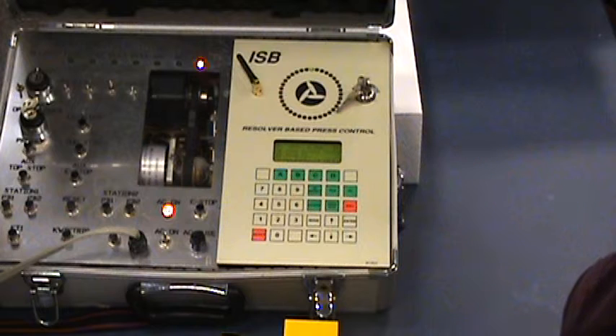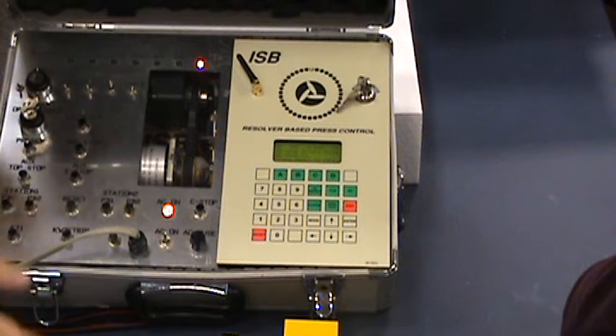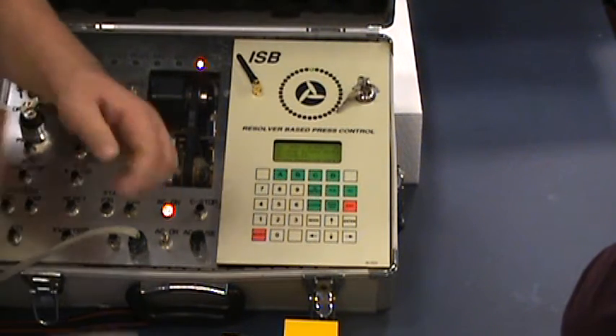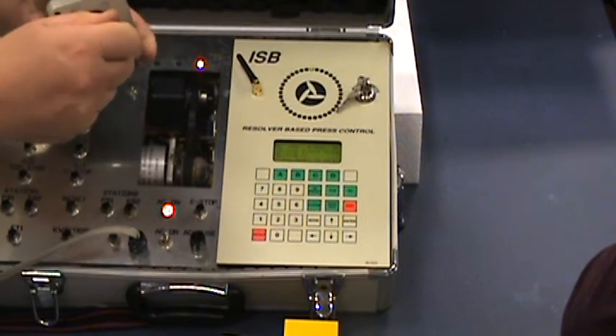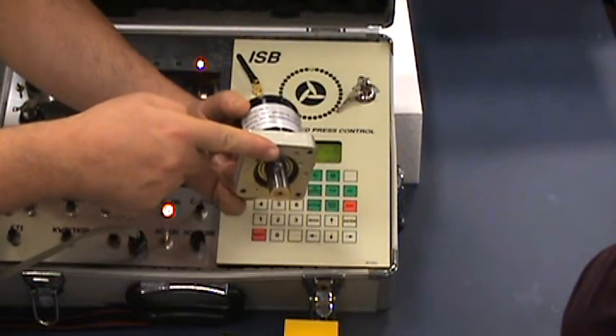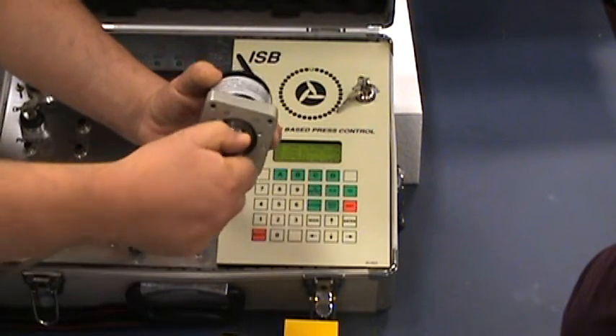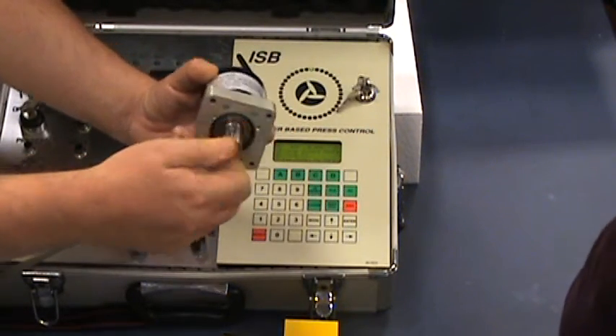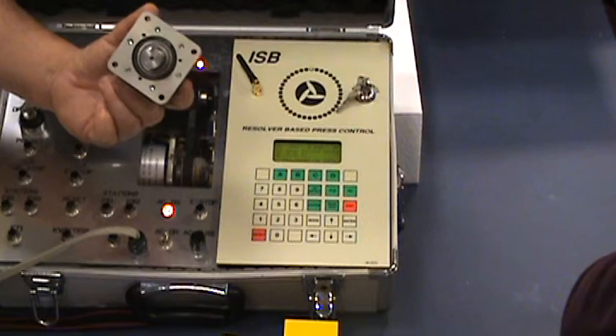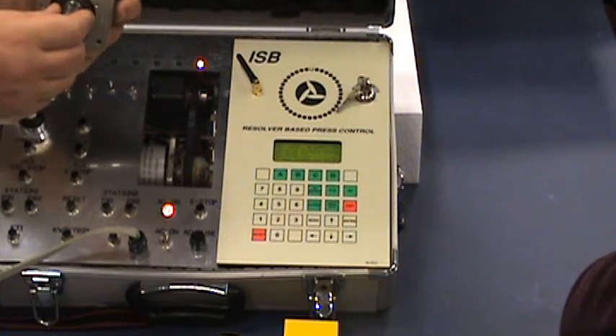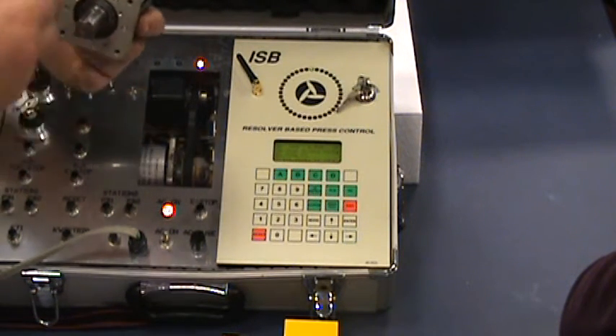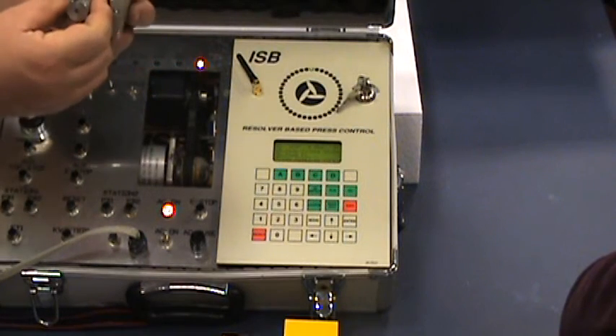There's a slight price advantage on the three eighths inch resolver, but the difference is the three eighths inch resolver never wants to see an axial load of more than 30 or 40 pounds. In other words, you don't want loads pushing perpendicular to the shaft, because it's eventually going to, you've got bearings on both ends of this resolver, there's bearings internally, there's two bearings. But if your weight's out here, it acts like a lever on that first bearing, and you're going to snap shafts. So 30 to 40 pounds maximum axial load on a three eighths inch resolver.